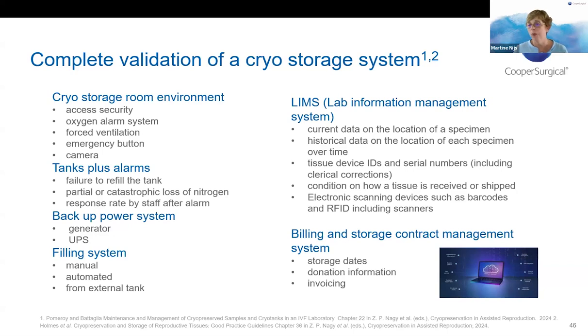The filling system can be manual, which is easy to check, but you have to check if your tank is full, so you have to log all of that. If it's automated, you still have to continue to do manual checks and validate. If you have a system where it automatically calls the company to say the truck will arrive and top up your tank, you have to create a false alarm or false order and see if things are happening. So you have to validate that as well. And then there is all the software linked to that, your laboratory information management system, and also your samples themselves. They need to have traceability. You need to know who owns these samples. Have they been paid? Is there informed consent for what happens to these samples in case of divorce or donation or whatever? There are tools to help you with that, but you still need to validate that it is working. That means you could do hypothetical cases. You do audits as well to see if all is in order.